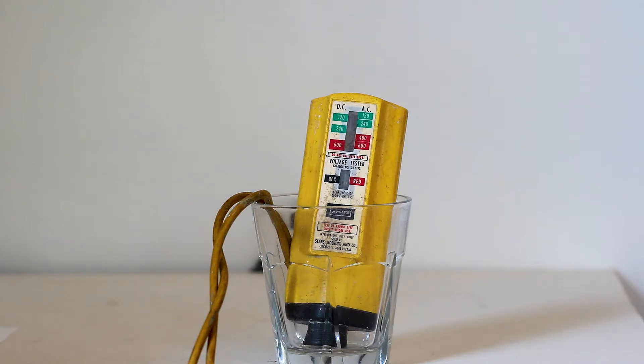An important fact about the solenoid voltage tester is that it is a low impedance instrument. This is in contrast to most multimeters with field effect front ends that have high impedance at the inputs. As a consequence of the low impedance, it should not be used on sensitive electronic circuits, but it does have an interesting application, which is testing an in-circuit GFCI.